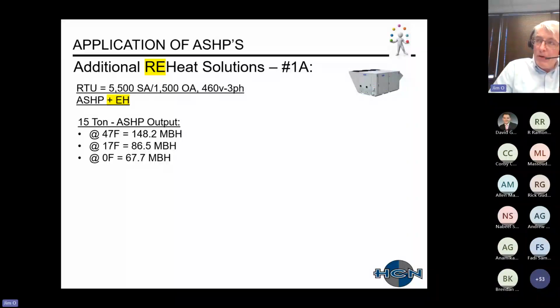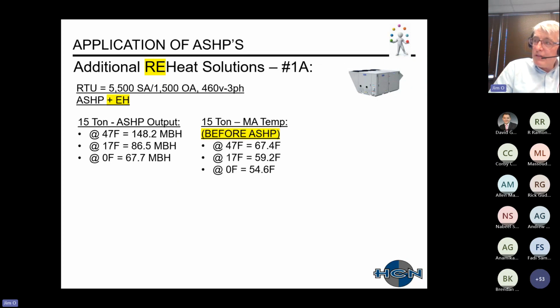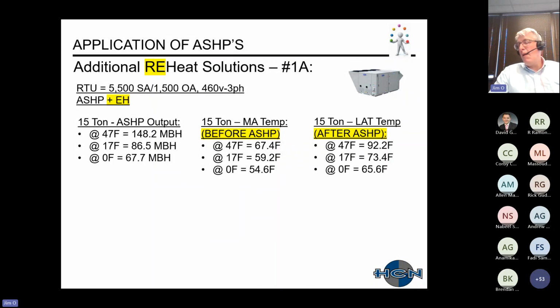So here's the output of our unit, 15 tons at those ambient temperatures. Here are our mixed air temperatures with those conditions from before, once again using Philly for my calculations here. These are our mixed air temperatures before our air source heat pump turns on. And then for my computer program, these are the leaving air temperatures of the air source heat pump after it is in heating.